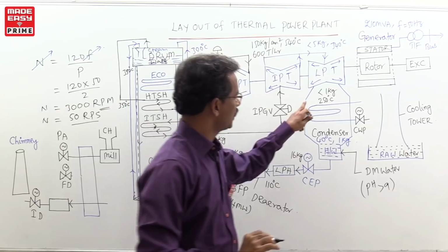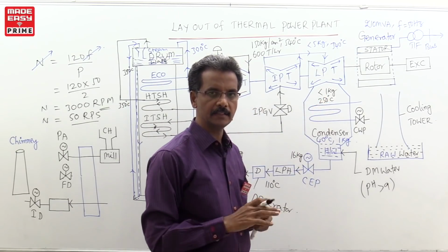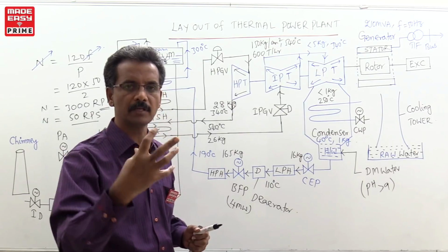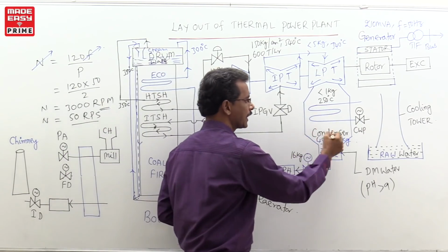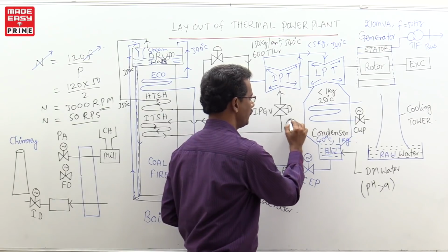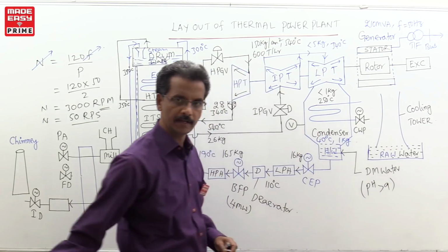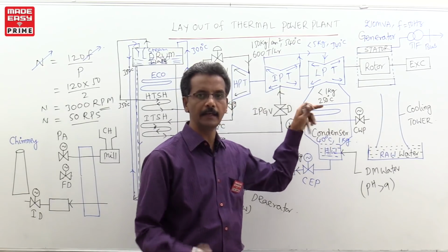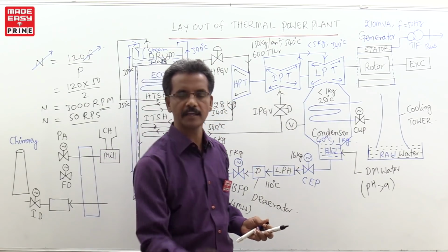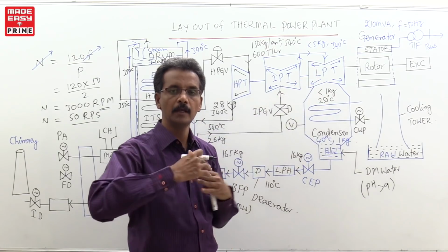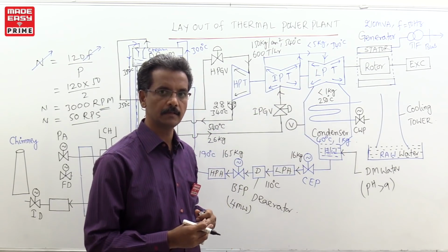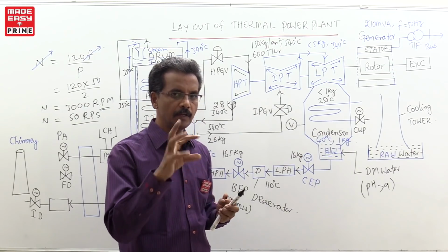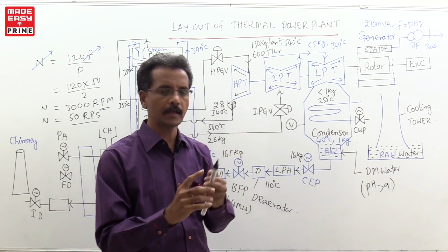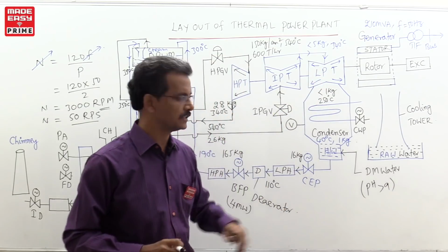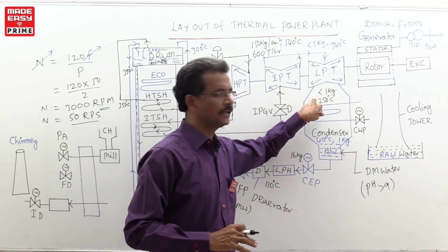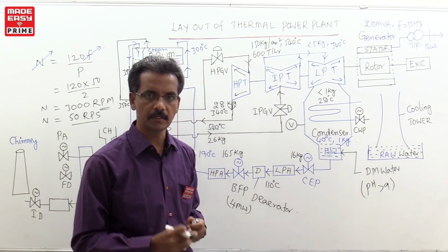Right. Now, you can observe that the pressure is less than 1 kg, that means it is less than atmospheric. How do we extract the steam? For that, a vacuum pump is maintained in the condenser. The vacuum pump maintains negative pressure inside the condenser, which is used to extract the steam from the LP turbine. It will improve the thermal efficiency. Vacuum creation is used to do the proper work inside the LP turbine, but the drawback for this condenser is that the 250 degrees centigrade steam is in a vacuum condition.